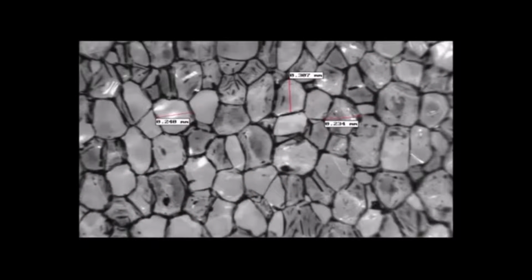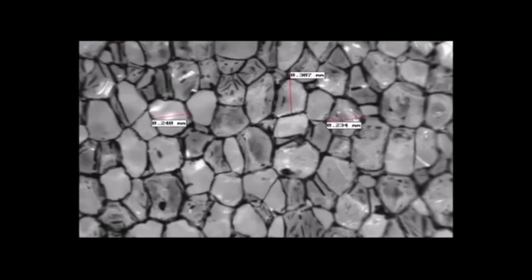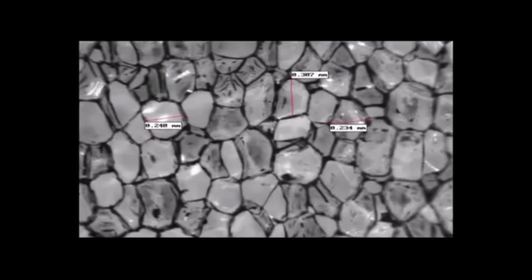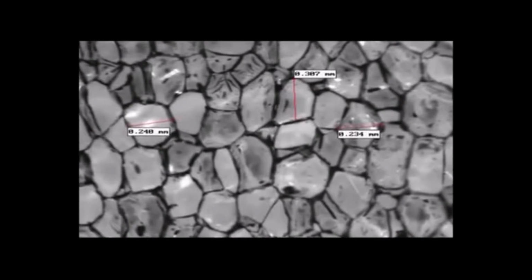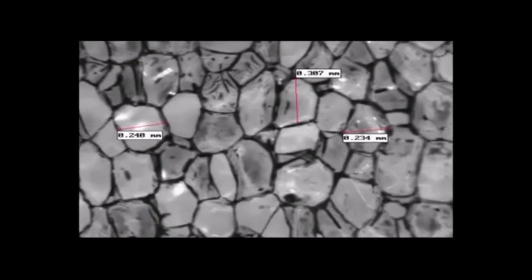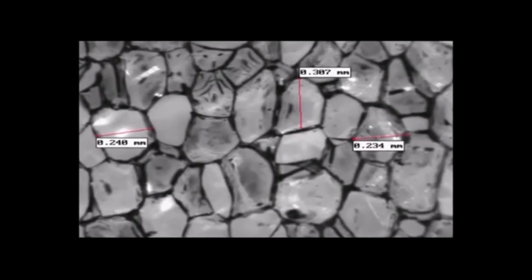With the XPS continuous extrusion process, a homogeneous closed cell matrix is produced through the entire cross-section of the foam. This matrix of closed cells resists water penetration, which is known to reduce R value if absorbed into the insulation.